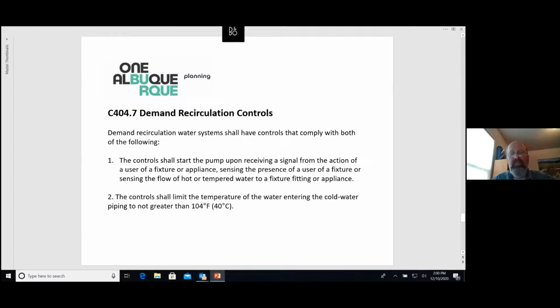So this goes more into the demand recirculation controls. I don't know if I've seen this so much in a commercial building, but I've seen it in houses where you have a little push button, and at the farthest bathroom you push the button, it starts on demand, spinning the water through the system, and it runs for a certain amount of time, and then it shuts off. So now you have hot water right where you need it. In essence, the same thing, probably a larger volume, and it limits the warm water that returns back into the cold water piping to 104 degrees, because you don't want to end up superheating this water. The hotter you get it, the more you circulate it through, the hotter it gets. There's no need for that, and code won't let you have water that hot.